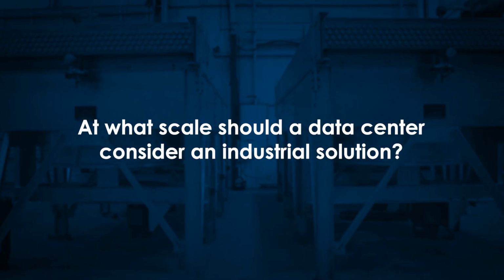Data centers should start considering an industrial solution somewhere around 30 megawatts. It's not that a commercial solution can't be deployed to get to a larger megawatt capacity - it actually revolves around the impact of higher recirculation off commercial units.